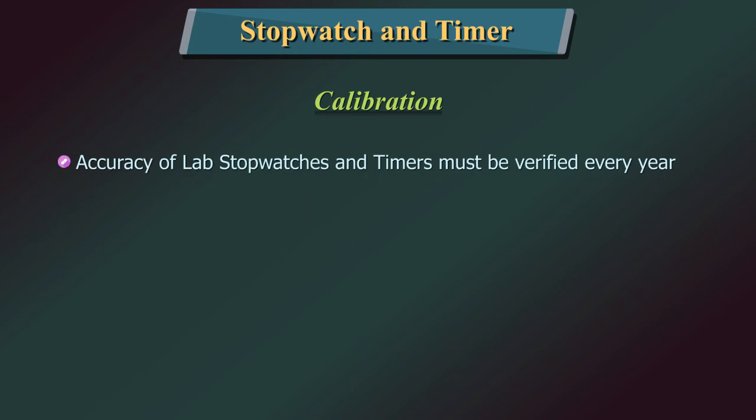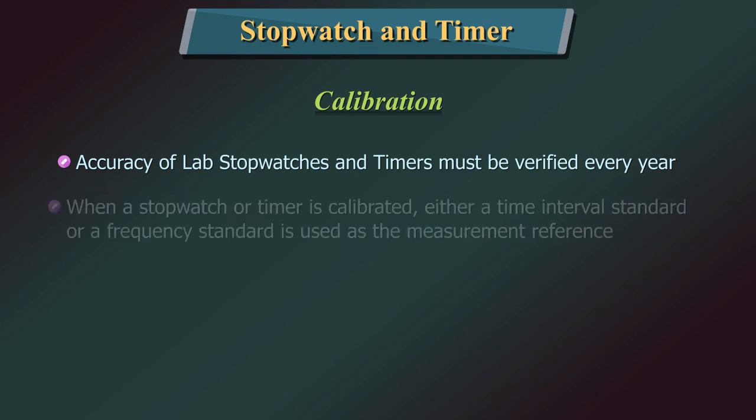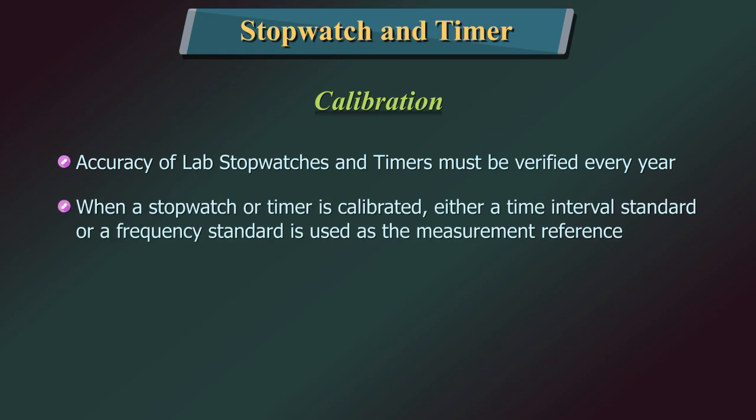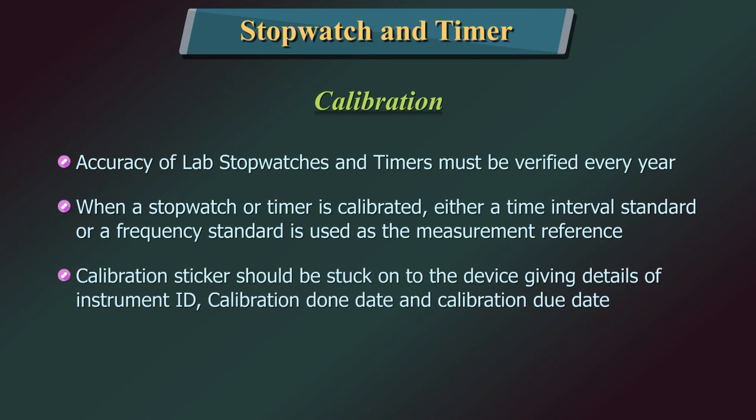The accuracy of stopwatches and timers must be verified every year. When a stopwatch or timer is calibrated, either a time interval standard or a frequency standard is used as the measurement reference. The calibration sticker should be stuck onto the device giving details of instrument ID, calibration done date, and calibration due date.